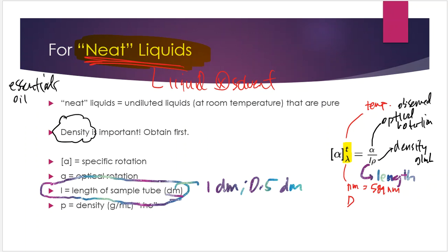Also notice that this is straight up density. It is not specific gravity. Specific gravity is very often reported in terms of, let's look at that number alone and report specific gravity and see if it matches. But this really by far is a density readout, not a specific gravity readout.